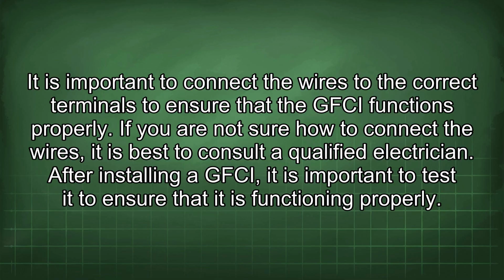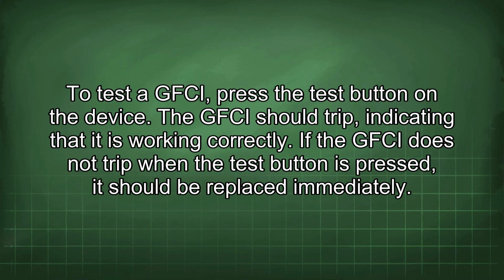After installing a GFCI, it is important to test it to ensure that it is functioning properly. To test a GFCI, press the test button on the device. The GFCI should trip, indicating that it is working correctly. If the GFCI does not trip when the test button is pressed, it should be replaced immediately.